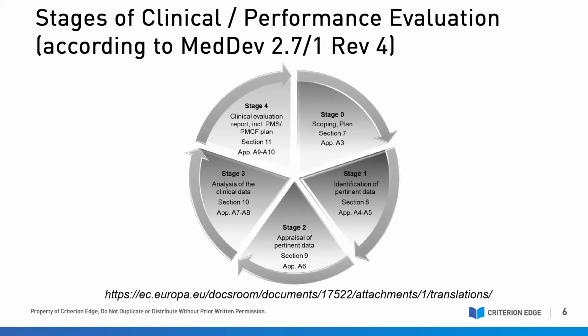As MedDev Rev 4 notes, each of those stages may be iterative. So new information can and often is uncovered, and that may require changes to expand the scope of the evaluation, or changes to the clinical evaluation plan, or it may even necessitate collection and analysis of additional data and appraisals. You may have thought that your tower was fully assembled, but what happens if you uncover a piece that needs to be added or removed at the very end? Clearly, it would be preferable to have a solid sense of how many pieces you're working with before you start building your tower. So really, that's where scoping comes in.